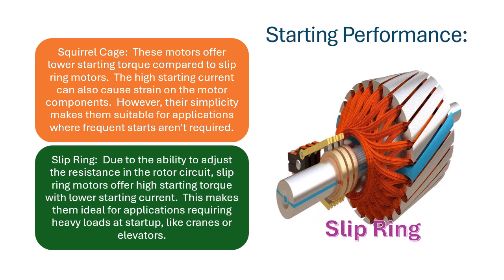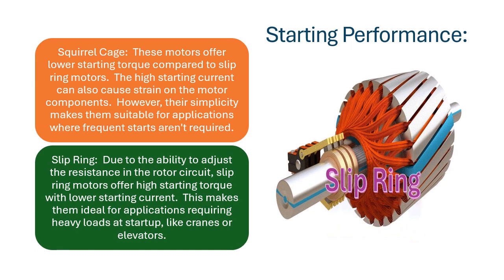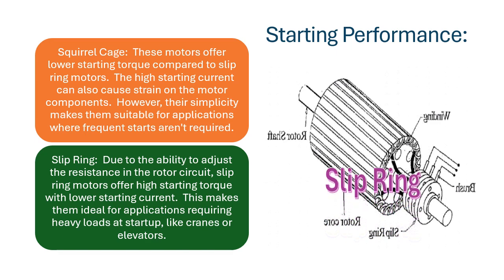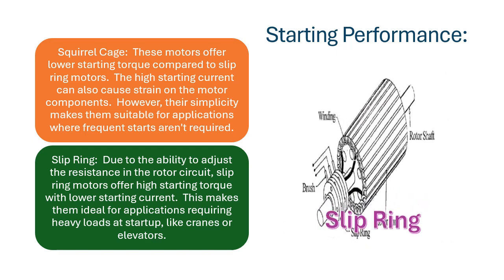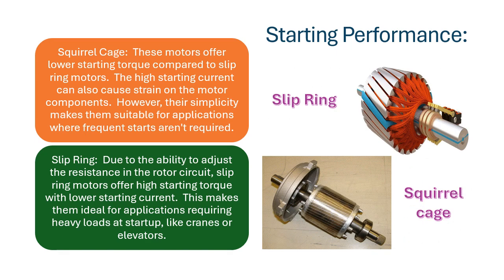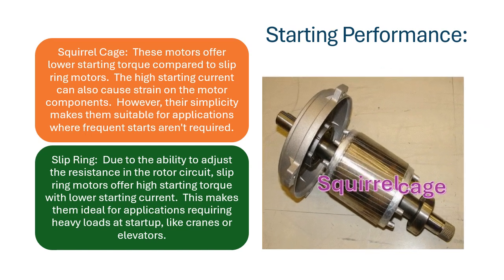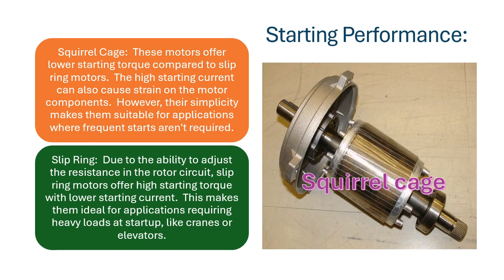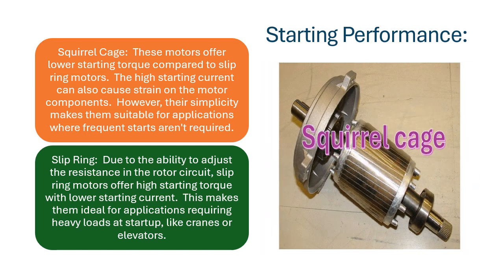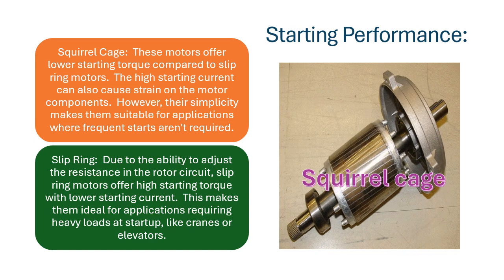Slip Ring: due to the ability to adjust the resistance in the rotor circuit, slip ring motors offer high starting torque with lower starting current. This makes them ideal for applications requiring heavy loads at startup, like cranes or elevators.